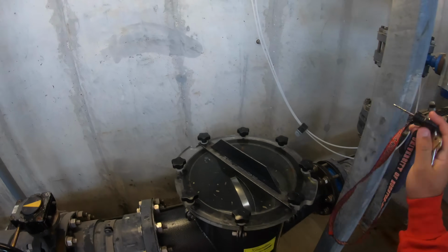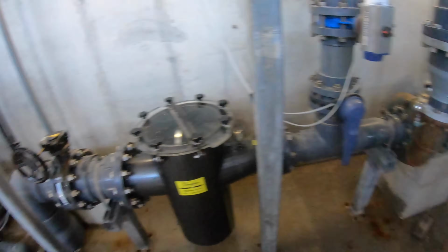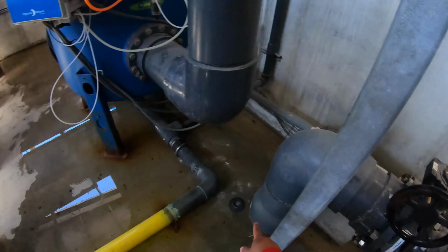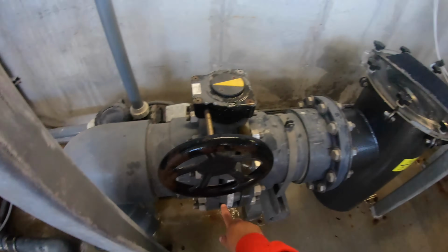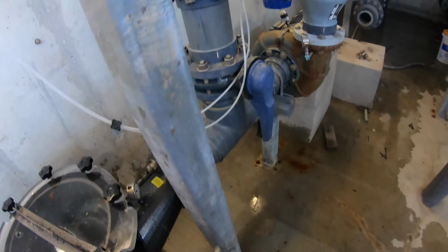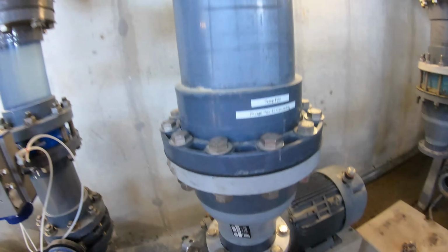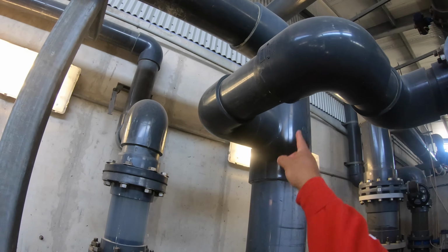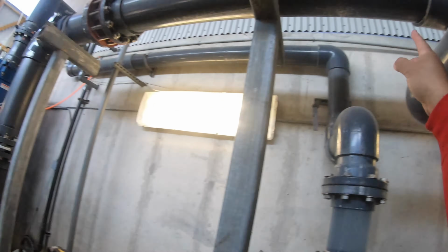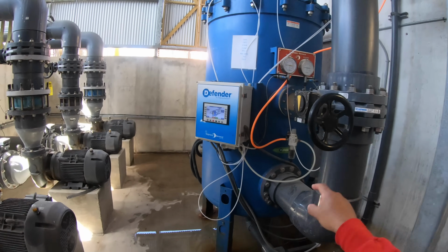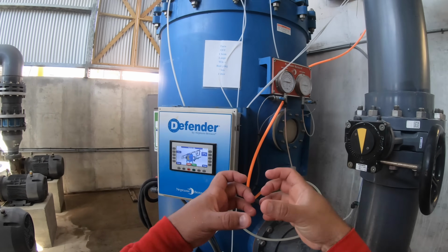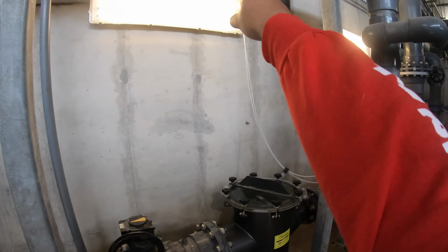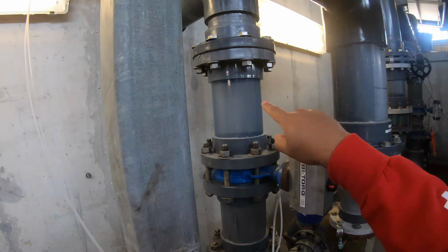Okay. So now what's going to happen is, again, let's talk about this. This is coming from the surge pit. That's where my source water's at. It's going to go through here, pass through the basket. The pump is going to pick it up, go across. Don't worry about this pipe. This is the drain pipe. You'll see it's off, right? That's going to go to the bottom of the filter, compressing all the media to the tubes, and then it's going to come back in this great 4-inch right here and pass through here.